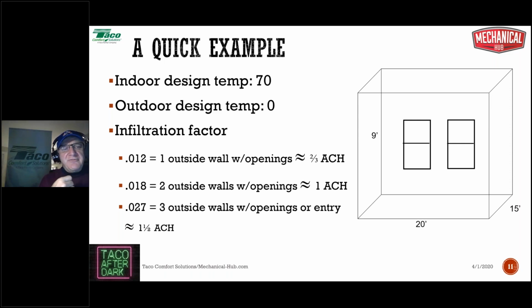You choose your infiltration factor based on how many outside walls have openings. It's not how many outside walls you have, and it's not how many openings you have. It's how many outside walls have an opening. If I have one outside wall with openings, which just by looking at the room we're looking at here, there's two windows in that one wall, we know that's the answer. It has one outside wall with openings.